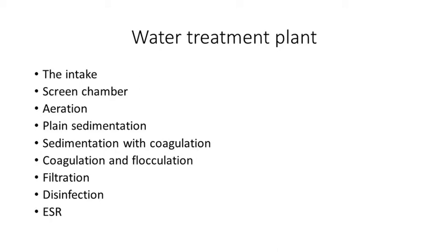The sludge and sediment deposited at the bottom of the tank can be removed from the outlet of the tank. Plain sedimentation also has various advantages. What are the advantages of plain sedimentation? Firstly, it reduces the cost of treatment. Secondly, it reduces the load on the next treatment units. It reduces solids by up to 60%. It also reduces some bacteria and some BOD.